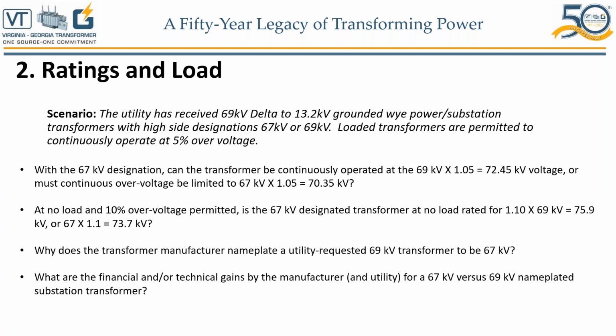what defines the nominal system voltage. And it is defined in IEEE standard C57.12.00, section 5.5.2. The voltage rating shall be at no load and shall be based on the turns ratio. When a transformer is provided with taps for de-energized operation, they should be at full capacity. So since the 69 kV we are talking about here is the high voltage side, and 99% of the transformers I deal with in the last so many years in this industry have de-energized tap changers, you do have the flexibility to go 2.5% per tap.